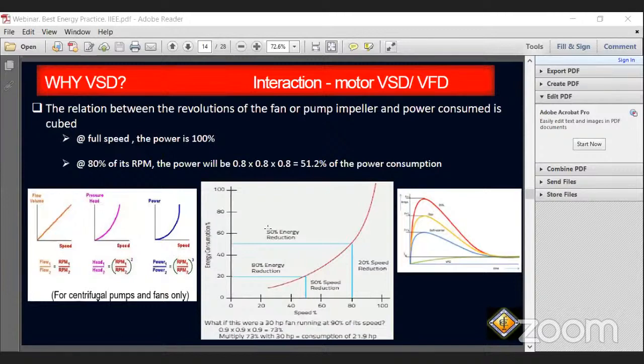As an example, you have a 30 horsepower fan running at 90% of its speed. Cube that, 0.9 times 0.9 times 0.9, that is 73%. Multiply that by your 30 HP. So the consumption is 21.9 HP. That's the advantage of using VFD because it is a cube of the power, cube of the RPM in the affinity law.